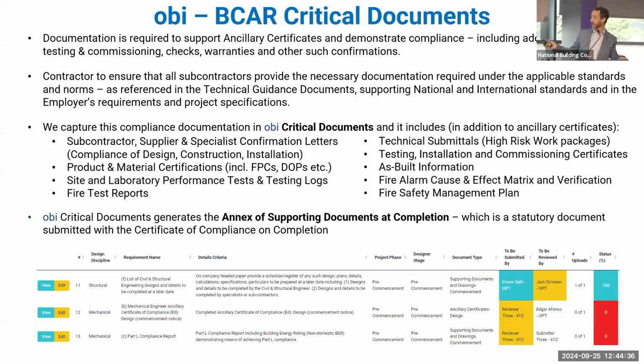The fire alarm cause and effect matrix - on the final issue, I've been on projects where that's got to Rev 15 or whatever it might be. They've made so many changes all the way through. You need to make sure the final issue of that cause and effect document is in the hands of the building owner and the person, people, or organisation that's going to come in and maintain their fire safety systems, particularly their fire alarm systems, because there are third-party interfaces that need to be ongoing checked. If they don't have the right version of that document, the building is not going to operate as intended for the life of the building. It's absolutely imperative this final version gets checked on an ongoing basis to make sure the system is working.